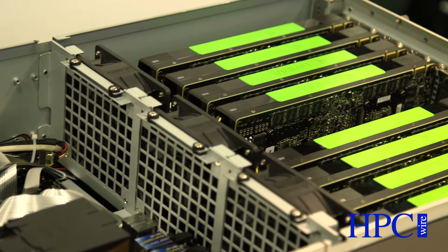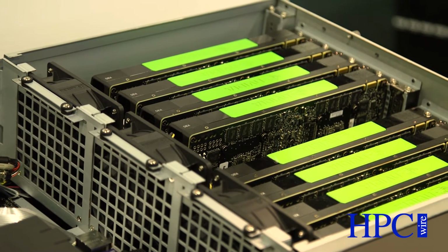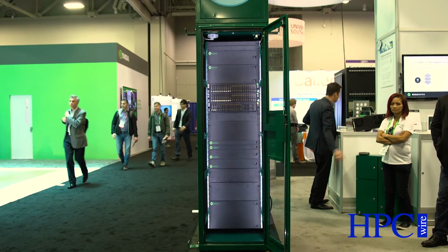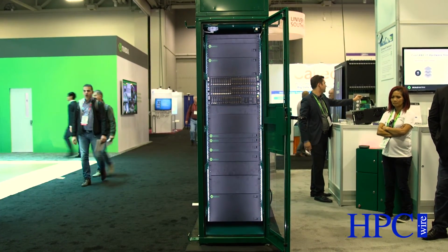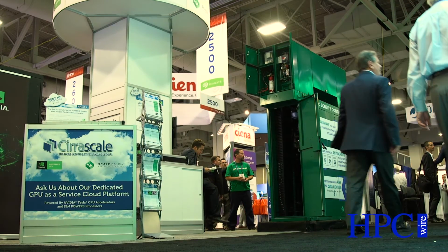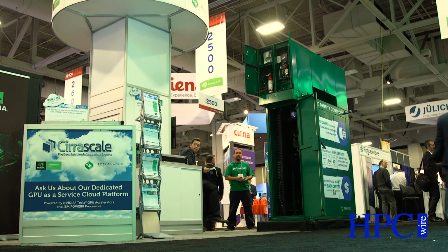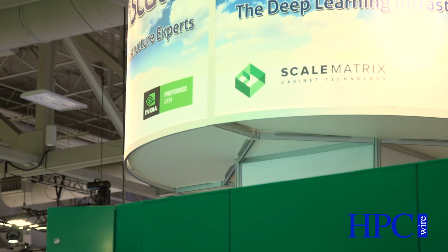Dynamic density control systems can be used for any normal data center usage, but they're best suited when you're looking at higher density workloads or variable density workloads where you can really take advantage of only using what you need. The system's designed so that it varies both the speed of the airflow as well as the water flow to the system, so you get maximum efficiency not only at the cabinet level but also at the data center level. You don't strand any assets when you're not using them, and this dynamic density occurs every second as opposed to having to make the big decisions during the actual purchase of the system and build out of the architecture.